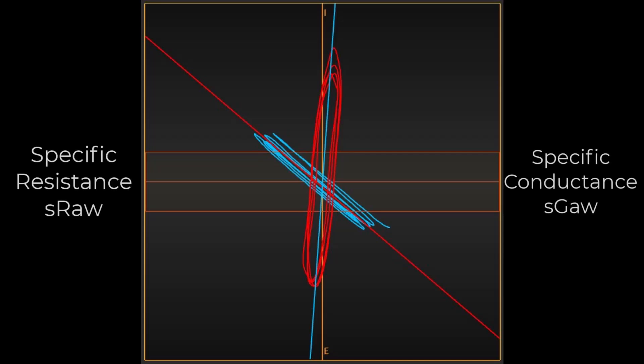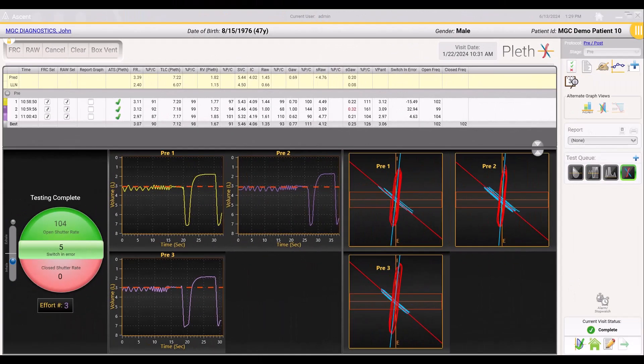Lung volumes are measured with airway resistance in order to calculate the volume of gas in the lungs during open shutter panting, which then allows the software to calculate specific resistance. Draw all of the efforts and look to see if any adjustments to the line of best fit are needed. The line of best fit is the same for the blue or closed shutter tracing as in lung volume testing — the line should use all of the data points and be the same angle or tangent.